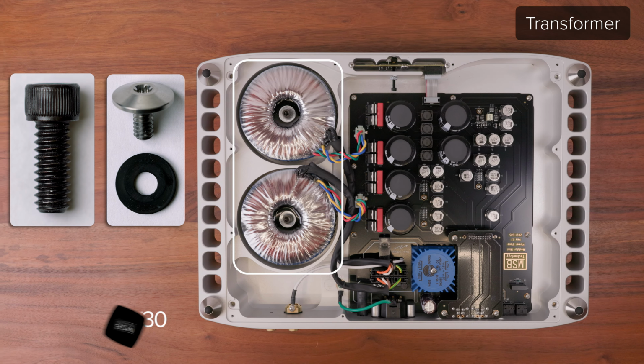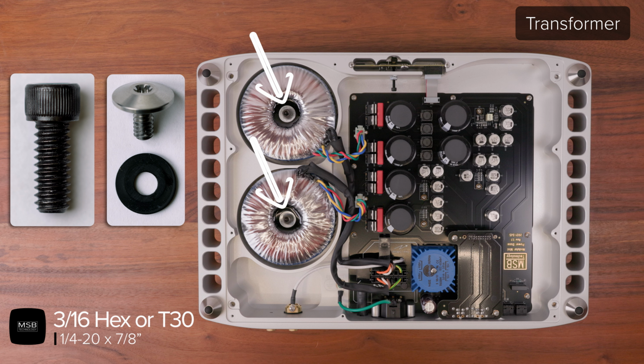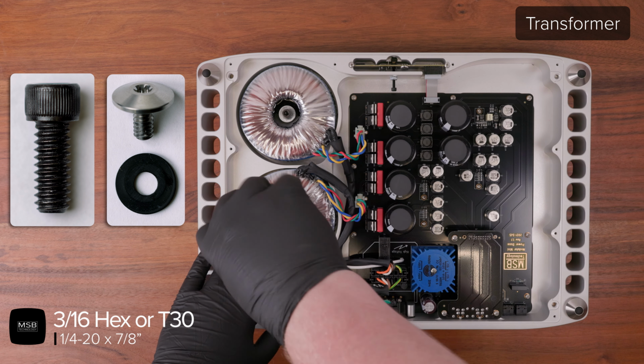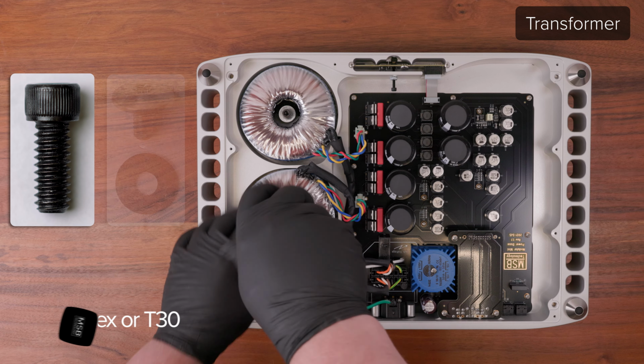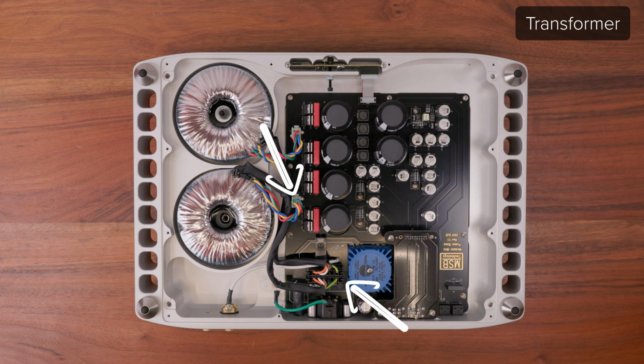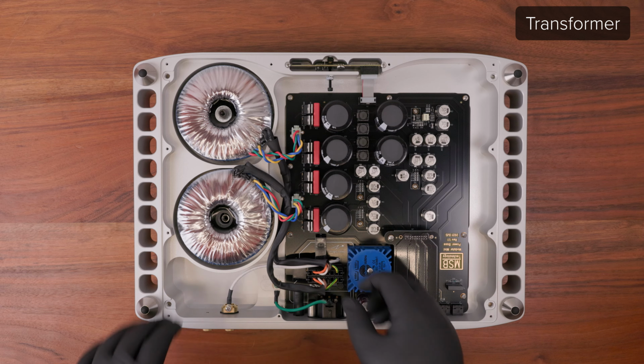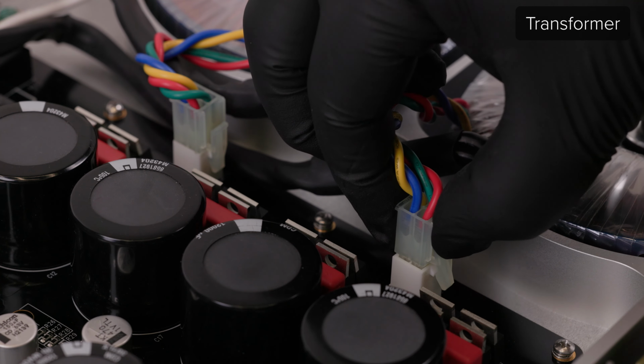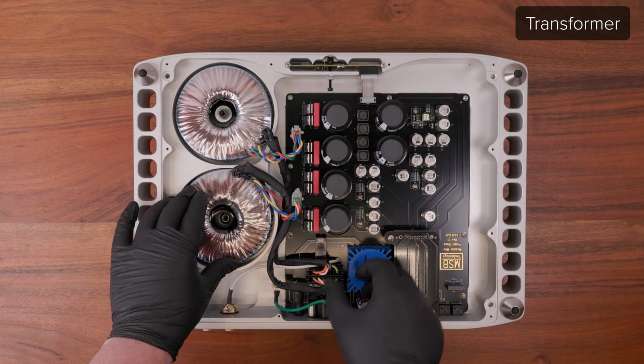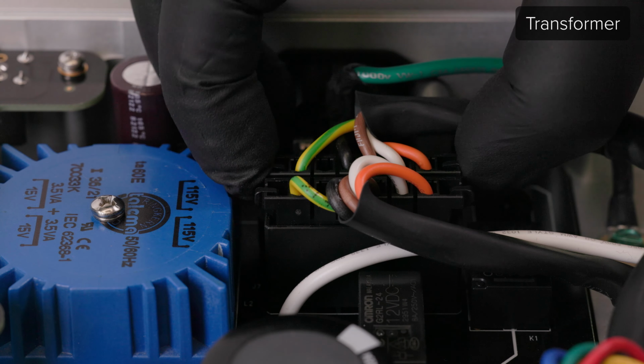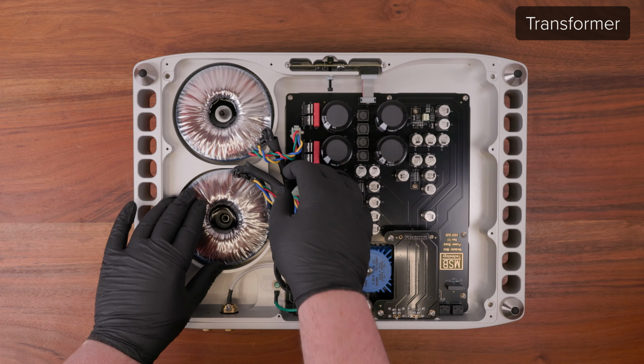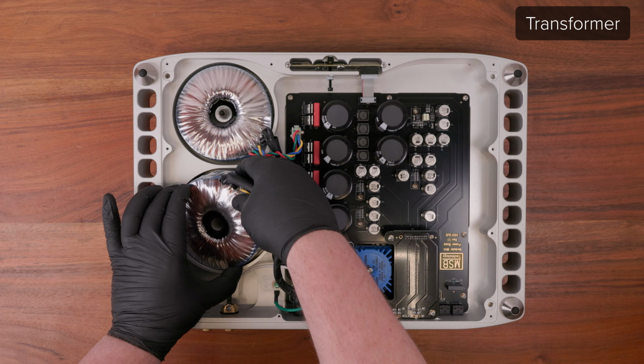To remove either of the transformers, use a 3/16 Allen driver to remove the appropriate 1/4-20 bolt and washer. Then, unplug the matching transformer connections. The white connectors can be removed by pinching the release tab on the side. The black ones require you to squeeze both ends of the connector to unplug them. Once unplugged, you can lift the transformer out of the chassis.